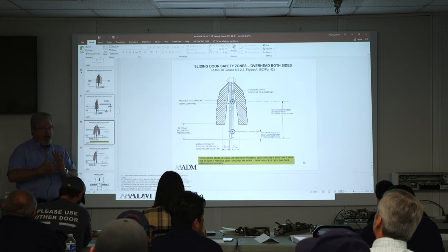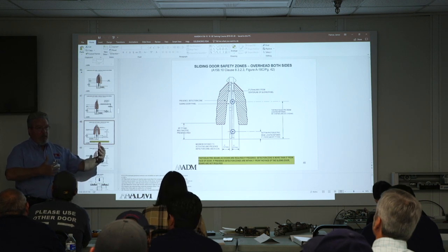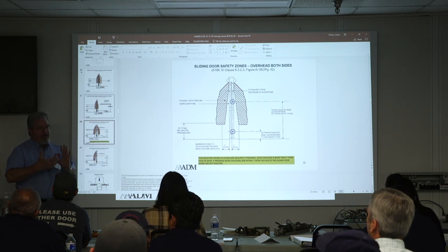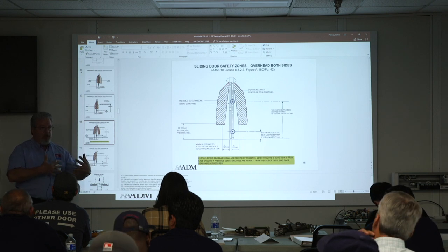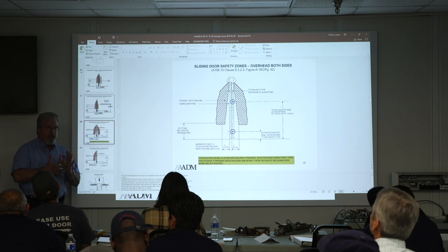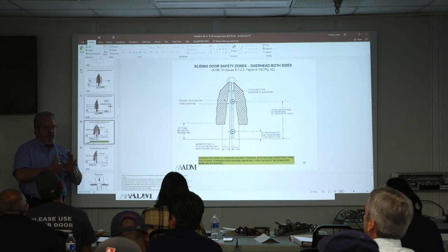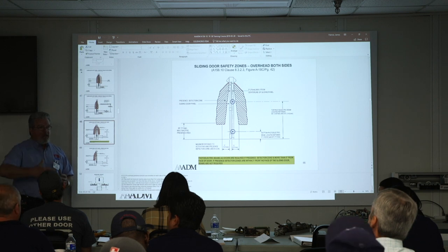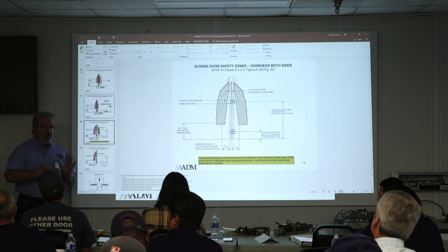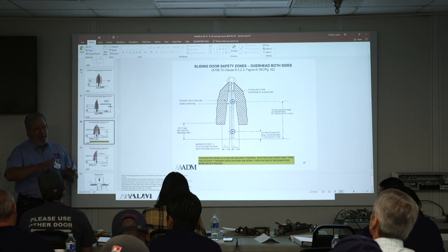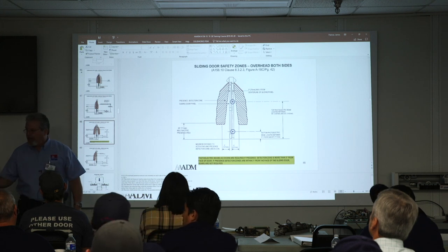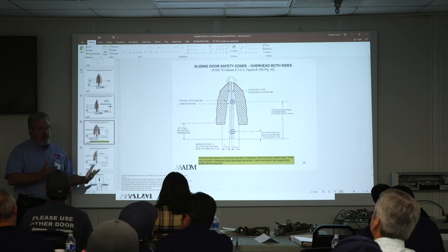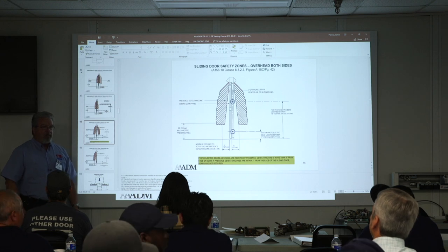The problem with making it way less, for the most part, is you get pressure differentials on a hotel or a building somewhere, and you get so much wind pressure or stack pressure against the door that if you have it set very, very low, the sheer force of the pressure differential is enough to restrict that door's ability to close. It interprets it as an obstruction and causes it to go open. So you have to set it high enough so that in the winter time, when you have more stack issues to deal with, it can overcome that, but not so high that it exceeds 30 pounds. The happy medium is somewhere in the 20 to 25 pound range for our products. You can get them to 15 on inside doors easily. If you have an exterior door that might have a stack issue, you're probably going to need to set it around 20. So it's not really considered a sensor.